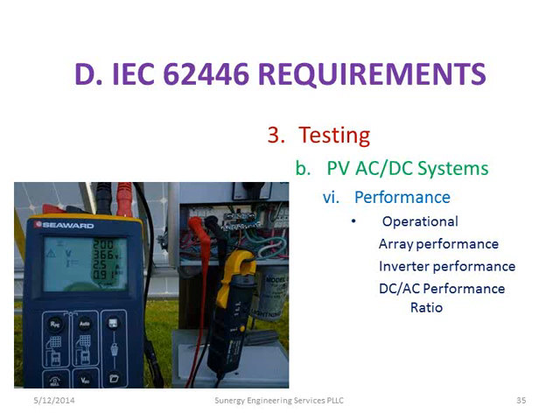Yeah, so right here it's actually giving the kilowatts because I've got the two probes on the positive and negative, and then I have the clamp on. And that's really convenient because you can get that reading instantaneous. And with this device, you can also be recording the irradiance and the temperature at exactly the time that you do the measurement, which is really helpful.